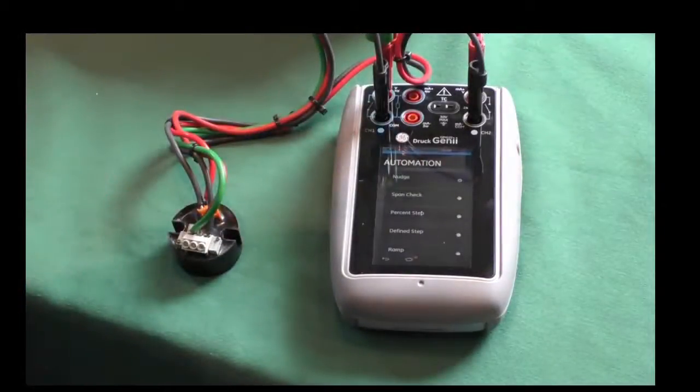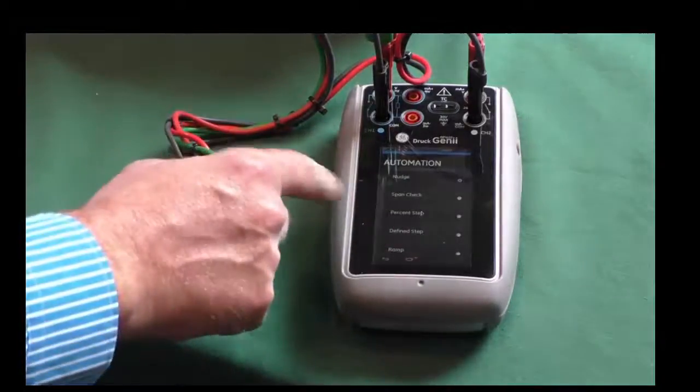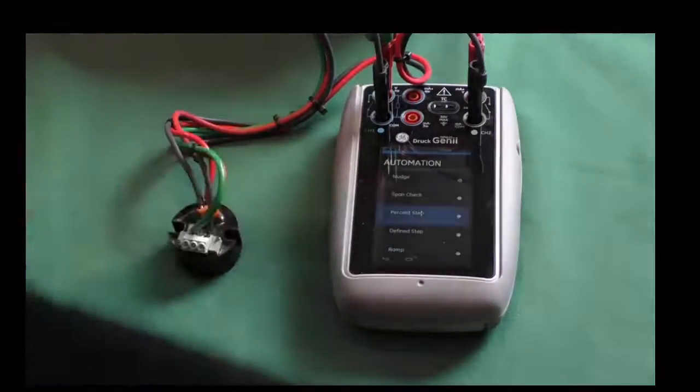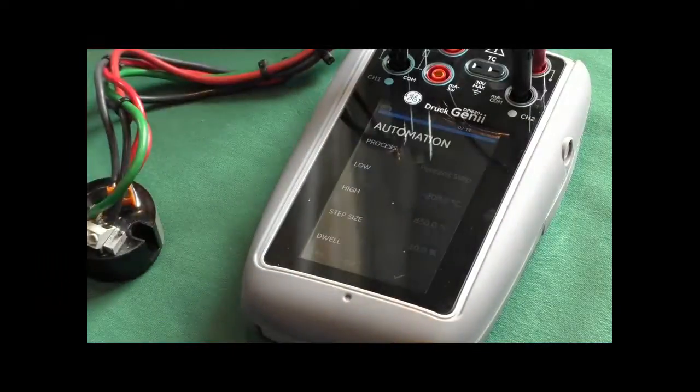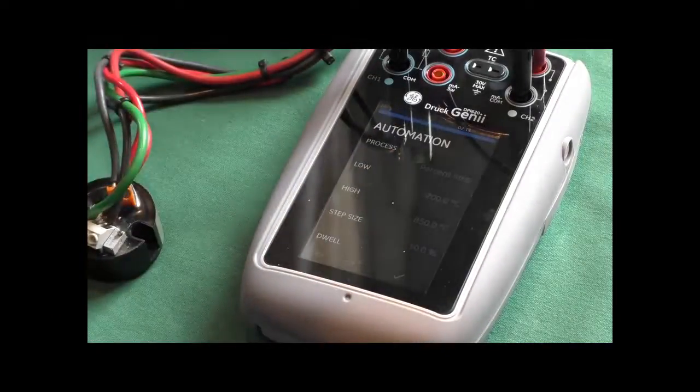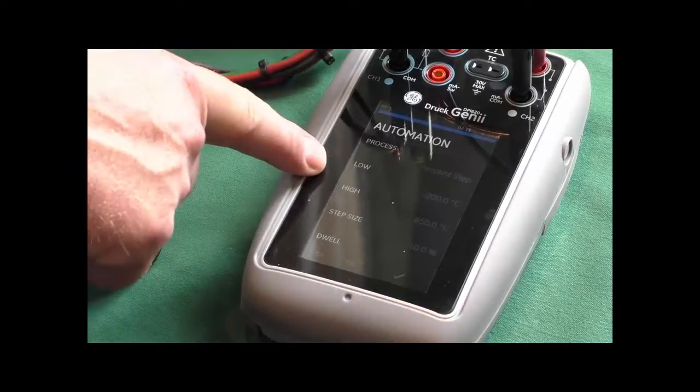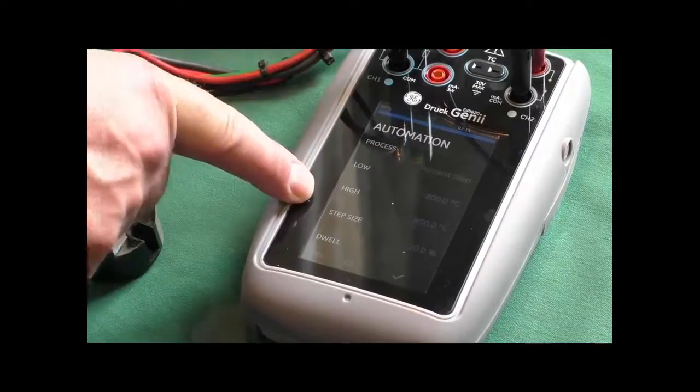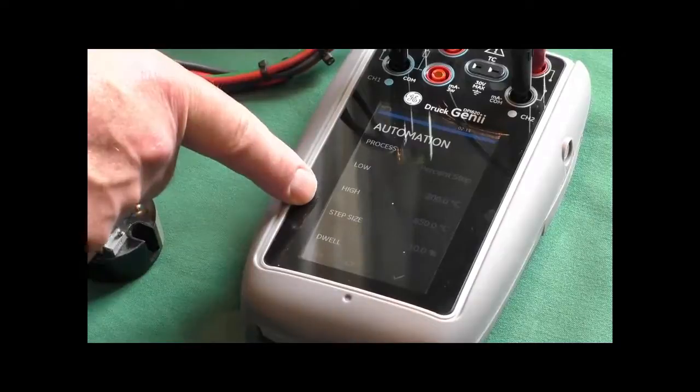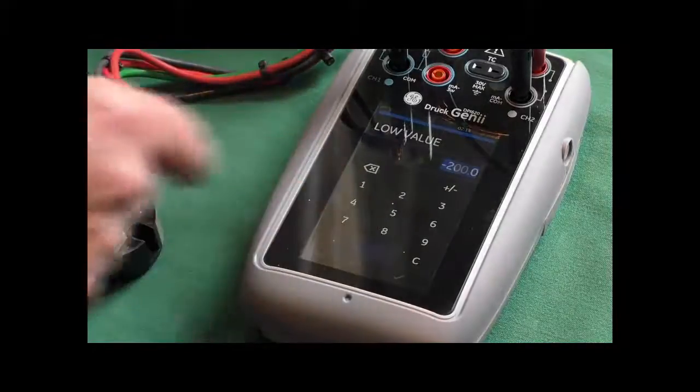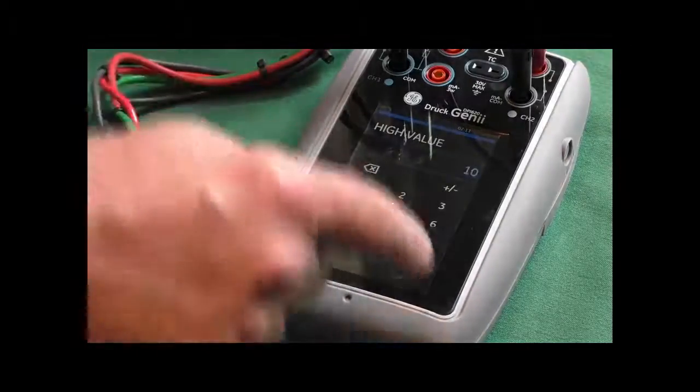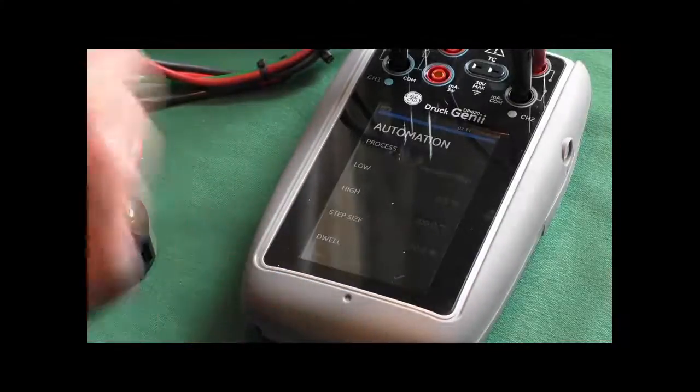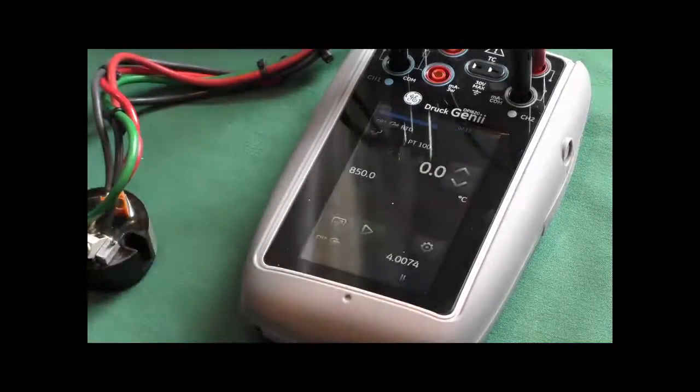And we can put a defined step in there, or we can do a simple span check, or we can do a percent step. So if we go into percentage step, the process is percentage step. At the moment, we've got the step size in 10%. The low currently is set at minus 200 degrees C, which would be 4 milliamps and 850, which is actually the full scale or the full range of a PT100. But in our case, it's 0 to 100 degrees C. So I need to go in and change that. So 0 is our low, and our high is 100. So we've stepped in 10% steps. Now if we come back, we accept this.